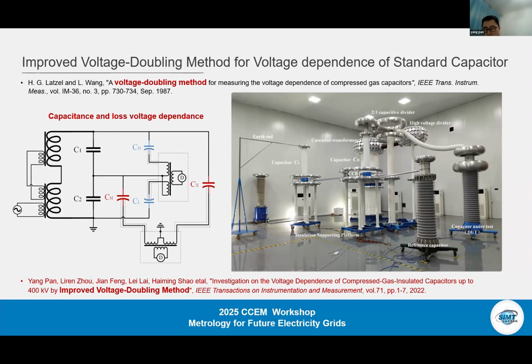So early implementations faced challenges operating above 50 kilovolt due to harmonic content. However, an improved voltage doubling method featuring a ground floating bridge with remote transmission for real-time monitoring of the 2-to-1 operating voltages has been successfully implemented on a new calibration platform up to 400 kilovolt, enabling accurate assessment of both the voltage dependence of capacitance and dissipation with uncertainty around 5 ppm.